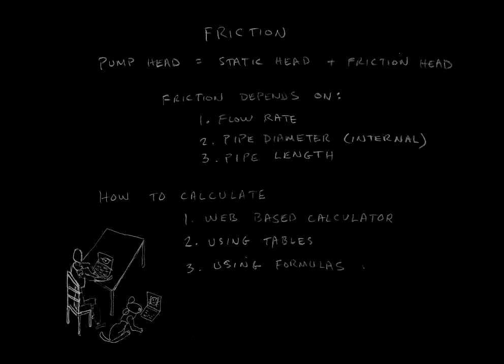The flow of a liquid through pipe involves friction, whether it's a small aquarium system or a giant industrial transfer system. The same principles apply. The amount of pressure that the pump needs to develop has to provide the energy for the static head plus the friction head. Without determining these two accurately, the pump you select will likely be undersized and you will not get your required flow. Now you can take a hit and miss approach and oversize your initial pump selection based on the static head or follow me through this easy approach to calculating friction.